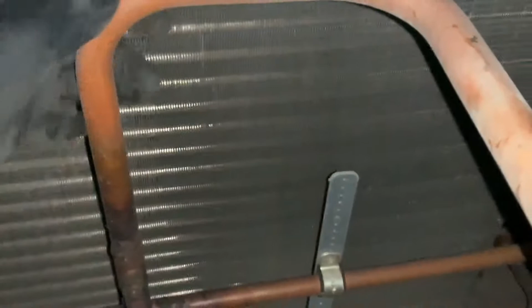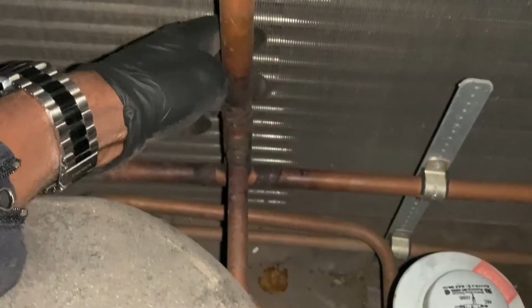So this is the compressor discharge line. It comes here, and you can see a T, right? There's a T right here, and it tees off, and we come into the DSCH on the headmaster valve. The other pipe continues down to the bottom, branches off, and goes into our condenser inlets.